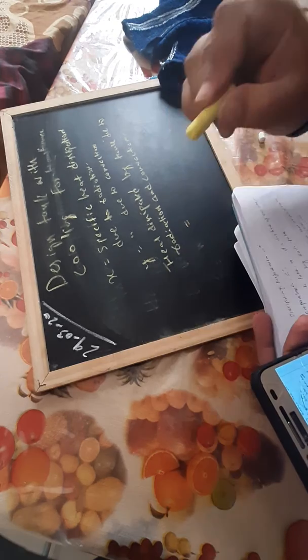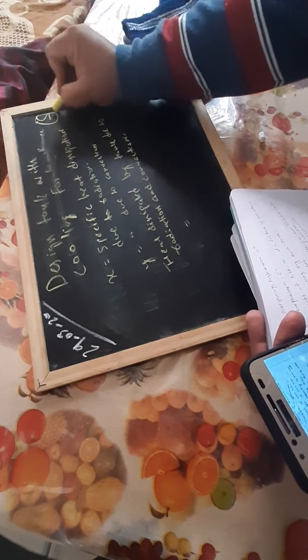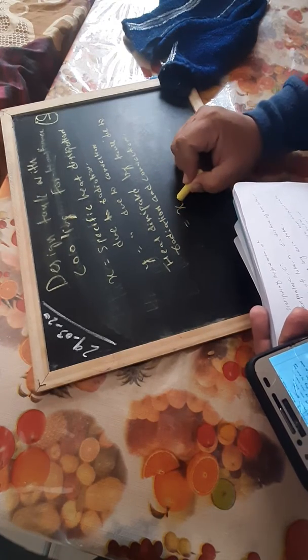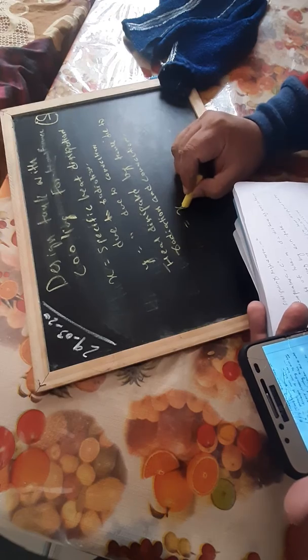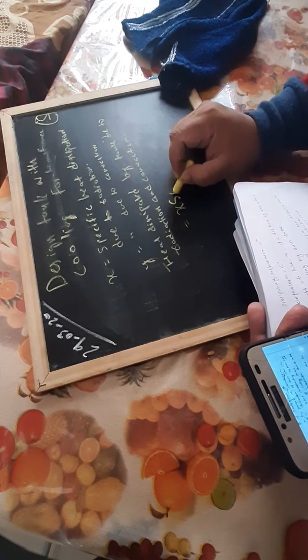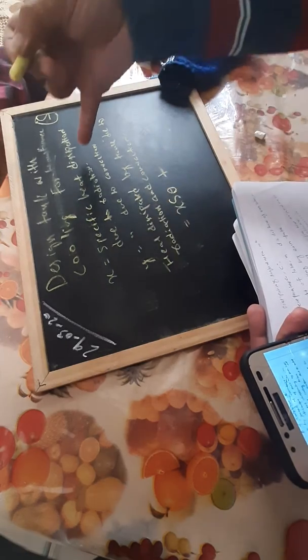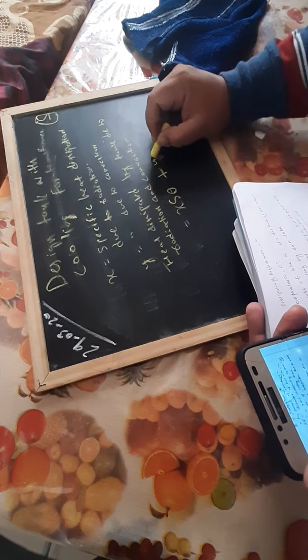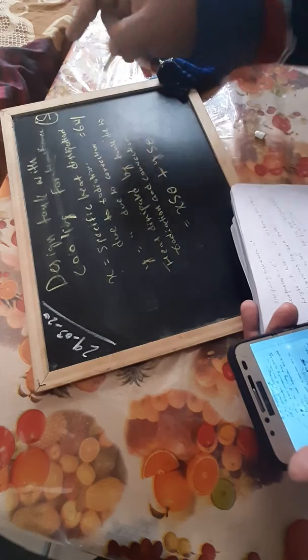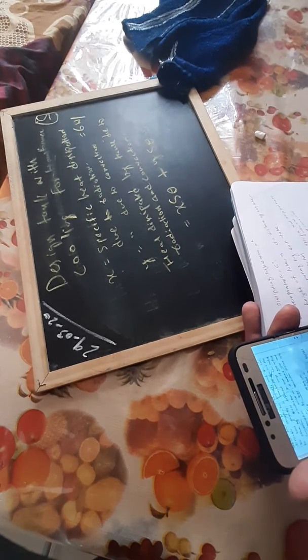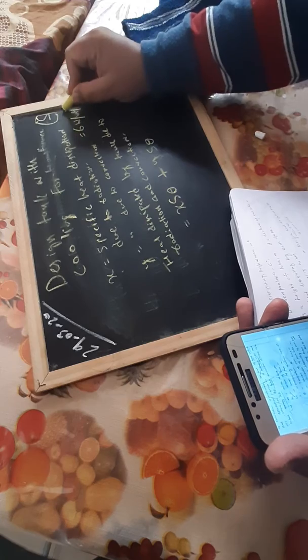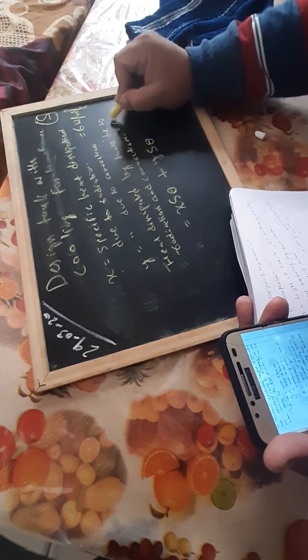Since the total surface area of the tank is S, the heat due to convection is X times S theta, and the heat due to radiation is Y times S theta. The standard values are 6 watts per meter square per degree Celsius for one, and 6.5 watts per meter square per degree Celsius for the other.